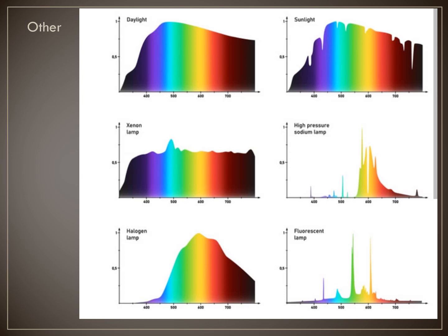In conclusion, if you want to decrease the application of cooling, you can consider the short arc xenon lamp which is much closer to solar irradiation from outside. You can choose optical filters to get wavelengths under predicted values.